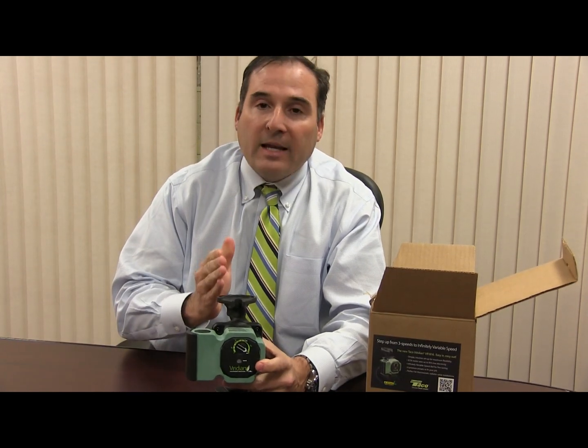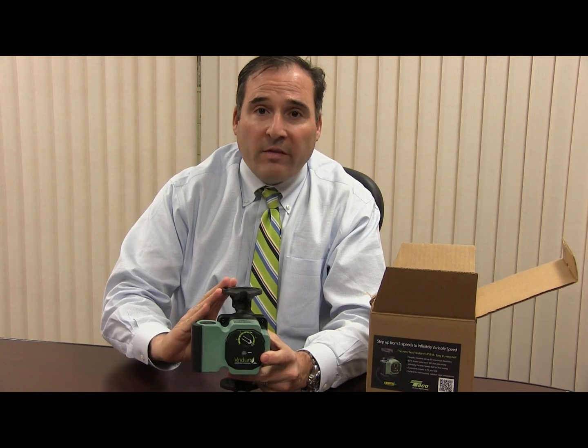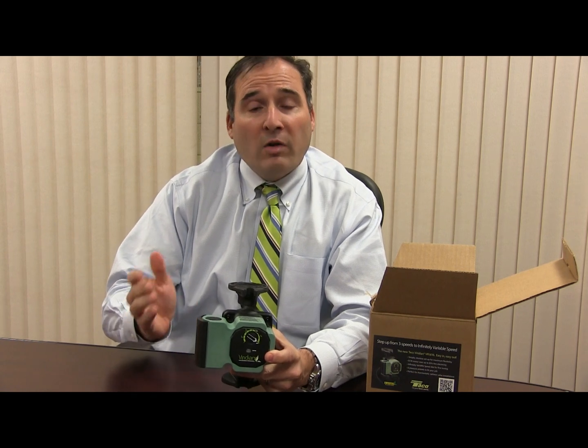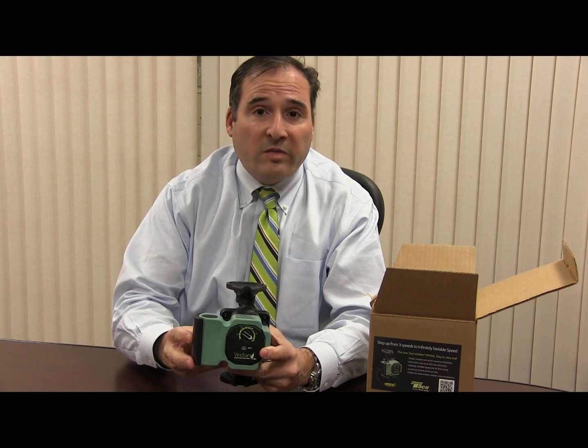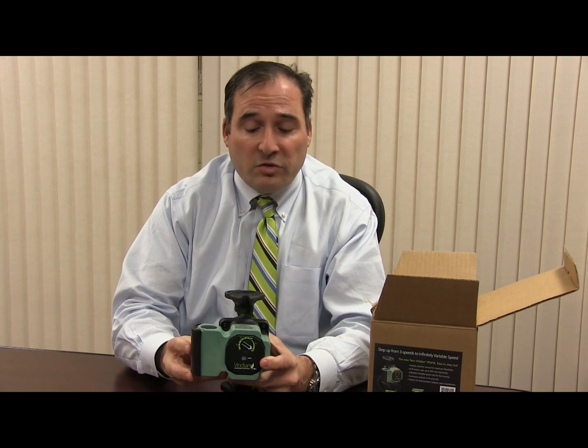The Viridian VR1816 is the exact same flange-to-flange dimension as a 007, 007 IFC, 0015, Grundfos 1558 FRC, and Wilo Star 21. It covers all of those ranges.